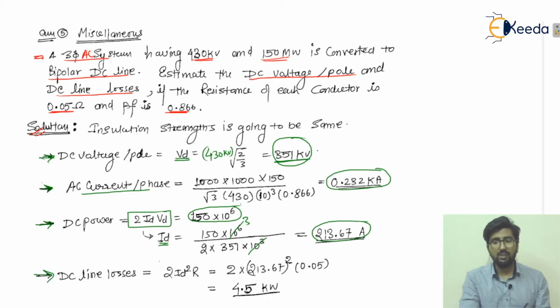Now let's find the DC line losses, using the formula 2 ID square R. We generally use ID square R, but since bipolar lines are used here, we multiply by 2. So: 2 into 213.67 whole squared into 0.05, the resistance value, giving us 4.5 kilowatts as the DC line loss.